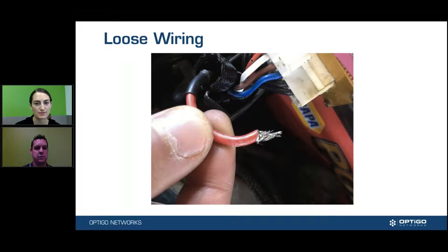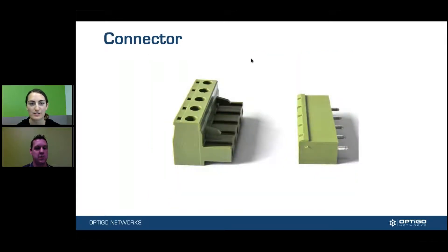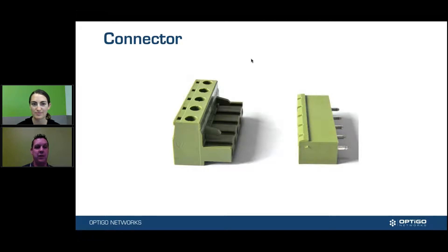So when you're having problems, go back and check — problems can happen at any time. Connectors are also another common source of the problem. Because these are low-cost devices, manufacturers don't always specify top-notch products for the connectors. They use low-cost connectors that don't always accept more than one wire, and there's a host of problems that comes along with that. You can't really change this, but you can use a couple of things to fix it — we'll get into that a little bit later.